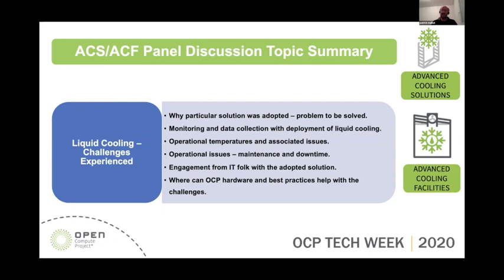But you still have to monitor for leaks at the rack level, and that has a cost. I agree with Jessica on this - you have to mitigate how much you're willing to pay for a risk that may or may never come. Technologies today, in terms of quick connections, are mostly dropless, made by very good companies that do this for a living, as well as fully soldered elements. These can be very consistent and leak-free for many years before you get any issue.